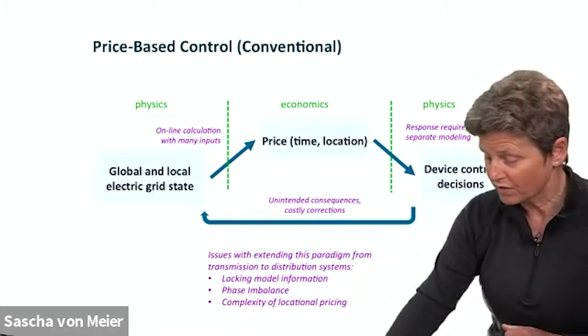In the phasor-based control concept, we're dealing just with physical measurements. And in a sense, that's analogous to the way that we control large generators with a voltage regulator and frequency droop control, where the machine is responding to quantities that it can measure rather than what somebody else calculated. And you may update set points later. It might take seconds or minutes to give a generator a different set of set point instructions, but from a moment-to-moment basis, the machine knows what it needs to do just by measuring.